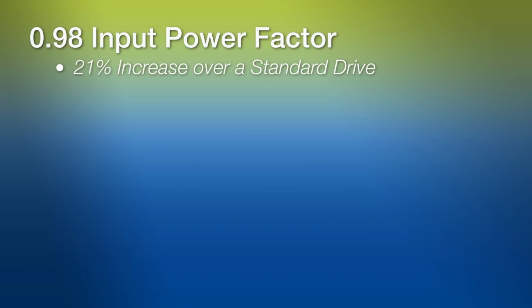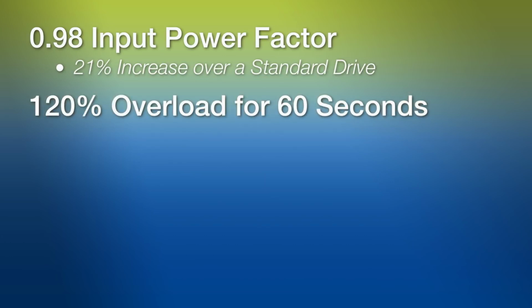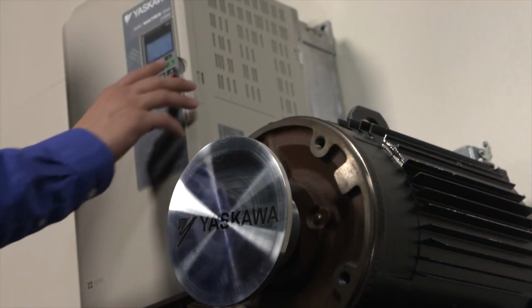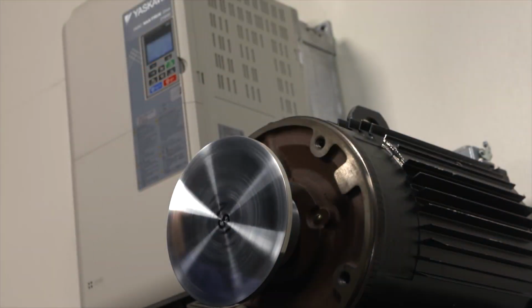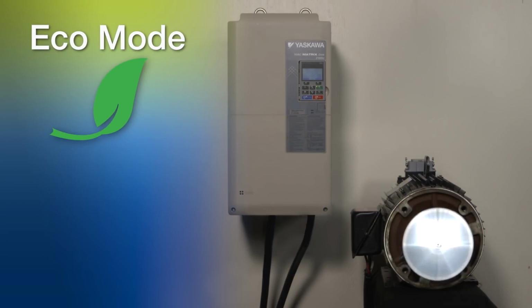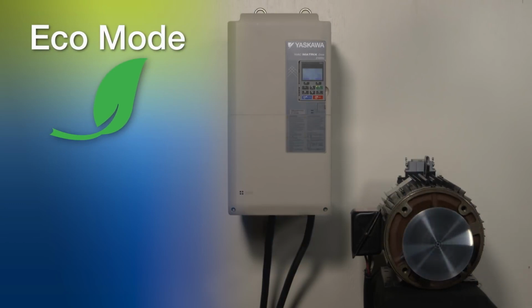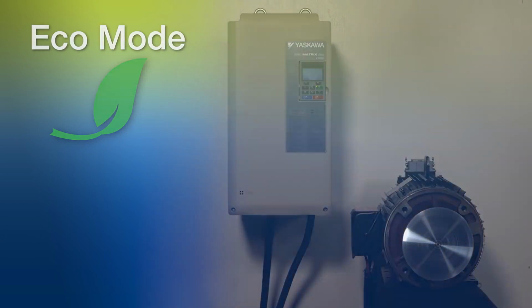The Z1000U offers 120% overload for 60 seconds. Motor auto-tuning can be used to tune the matrix drive to the connected motor's specifications, resulting in the highest performance possible while maintaining maximum efficiency. The Z1000U also has an eco mode. When running an application near 100% speed, the Z1000U will activate eco mode to achieve near across-the-line total harmonic distortion. In turn, this will result in low audible motor noise and lower current.